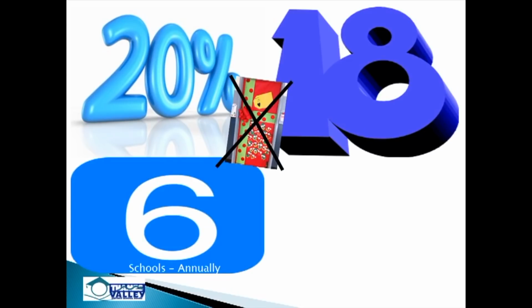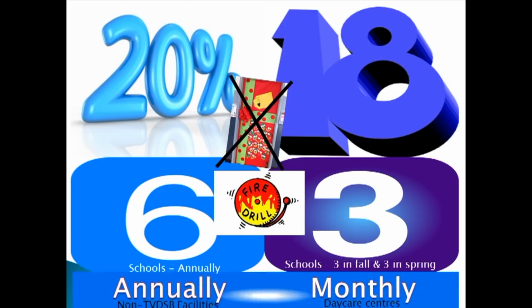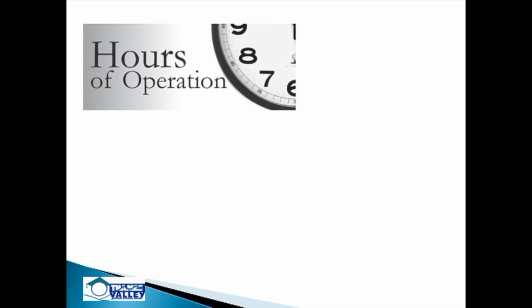Schools shall conduct 6 total evacuation fire drills each year. 3 of these drills will occur in the fall, and 3 will occur in the spring term. The first fall term evacuation drill should be held early in the school year to ensure that students are familiar with proper evacuation procedures. Fire drills shall be held during operating hours when the school is occupied by students. It is encouraged that schools practice alternate exits during these drills.